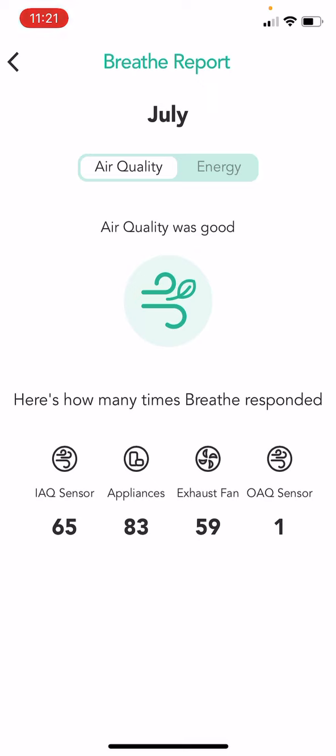That's what we just touched on a minute ago, where the system notified me that the outdoor air quality was not acceptable. And that happened one time, you see here, with PM 2.5. Knowing that I have MERV 13 filters, I just enabled it and let it run. So that equates to about 208 runs, if I'm doing the math right, with 65 of those being indoor air quality sensors. Looks like about a third of the time we run off of indoor air quality sensors driving the service to run.